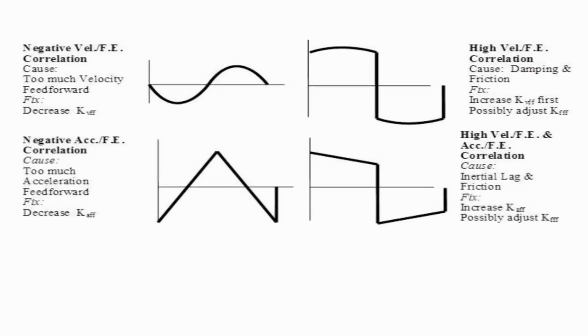The top left corner shows a response that is the opposite from the diagram in the top left corner of the previous slide. This shape is due to having too much kVFF, so decrease kVFF until the valley on the left and the peak on the right both disappear, and the following error oscillates about zero.